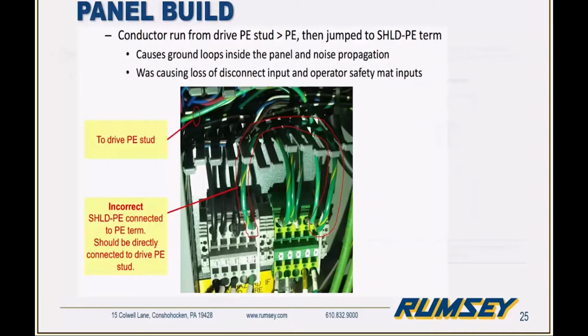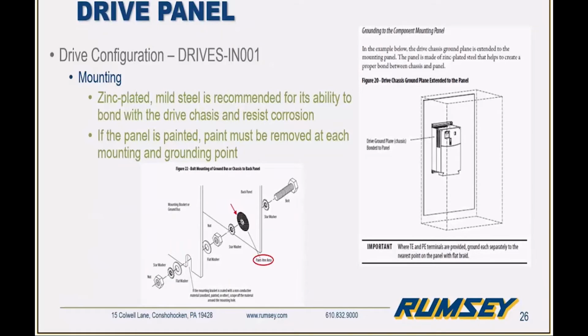One other thing to note in the panel for drives is the use of a back panel. Rockwell recommends using a galvanized panel to mount the drives to, in order to allow for a better grounding point. This is a better solution than using a painted panel, because many times with a painted panel you're going to have to remove the paint at any mounting point or grounding point, and it also opens up area for corrosion to occur.